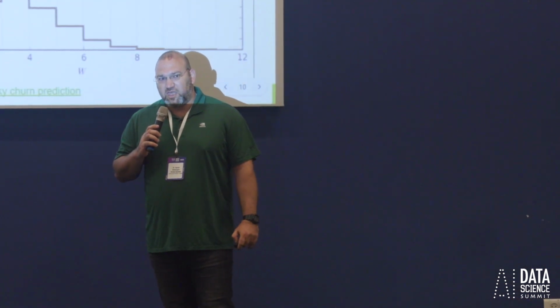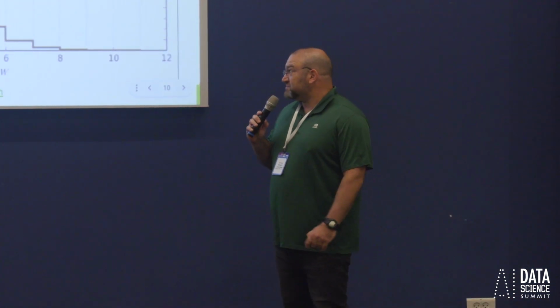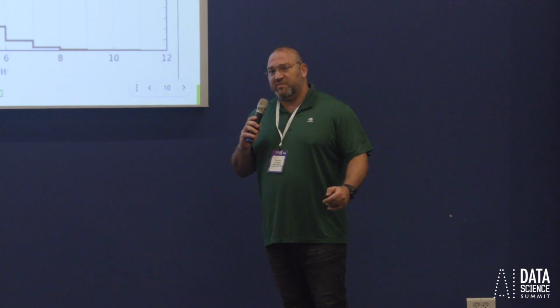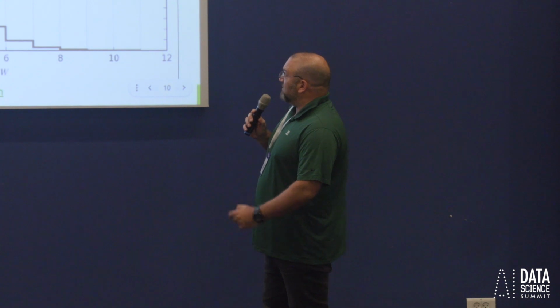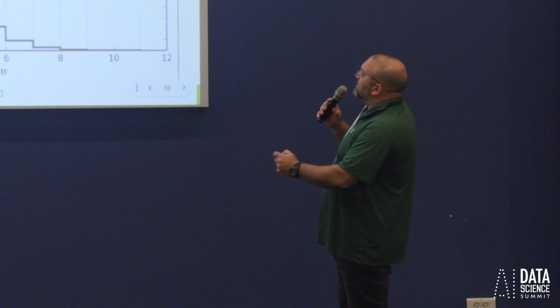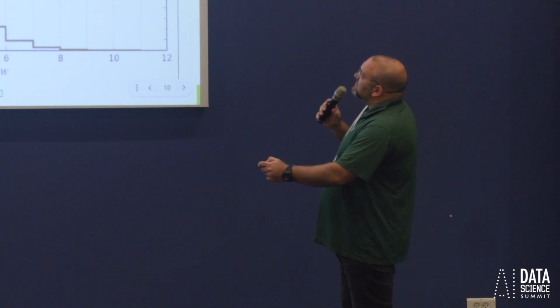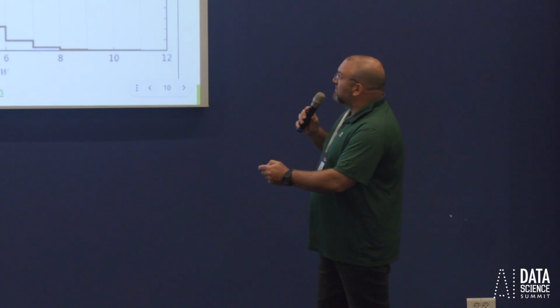Think about a cable in a data center. There are like 200,000 cables in the data center. The older the cable is, the more likely it is to fail. So this is when beta is larger than 1. So let's go back to the hazard function. Instead of writing the distribution, I can write a hazard function. And you can see when beta is larger than 1, then the hazard goes up. When beta equals 1, it does not depend on t. And when beta is lower than 1, then it goes down. I'm almost out of time, so let me go faster.